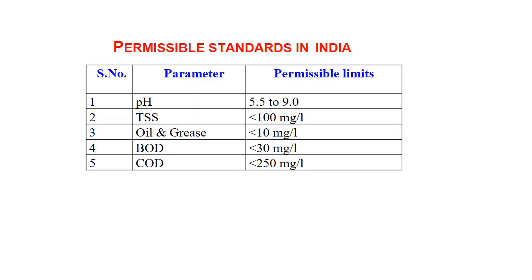Here we can see the BIS standard for discharged or treated water: pH 5.5 to 9, total suspended solids less than 100 mg/L (100 ppm), oil and grease at 10 mg/L (10 ppm), BOD less than 30 mg/L (30 ppm), and COD less than 250 ppm.